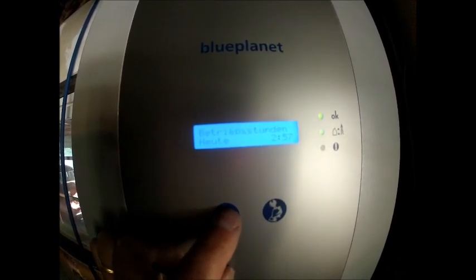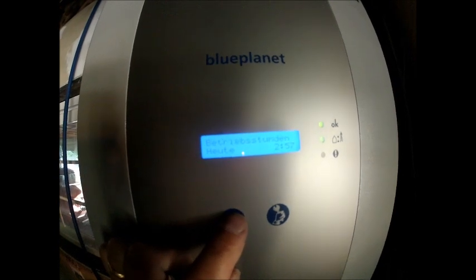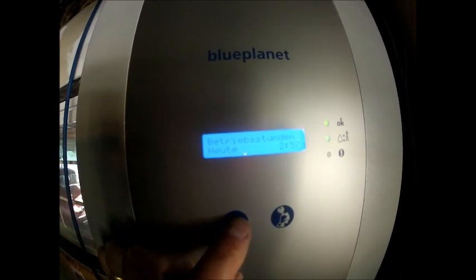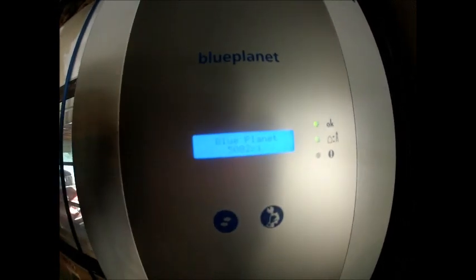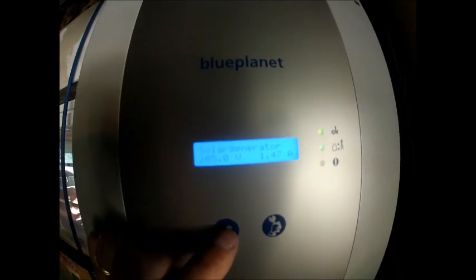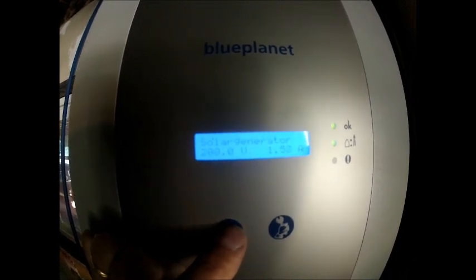This 258 hours and 19 minutes is the total time the inverter's been running since two weeks. That's the number of hours today since the inverter was started up. It's been low sun, so it basically starts feeding back as soon as any kind of light hits the panels. On the DC side, the solar is at about 200-and-something volts and 1.5 amps right now. That'll boost up a little later, closer to 400 volts and about 5 amps.